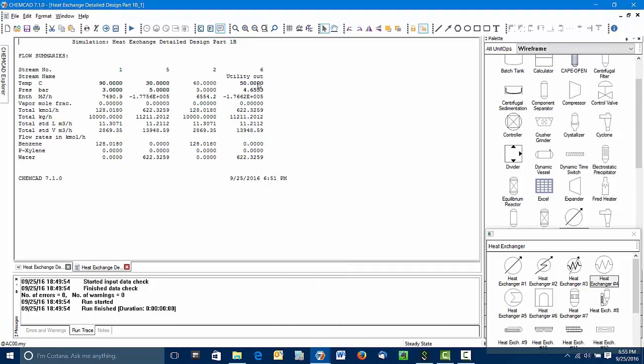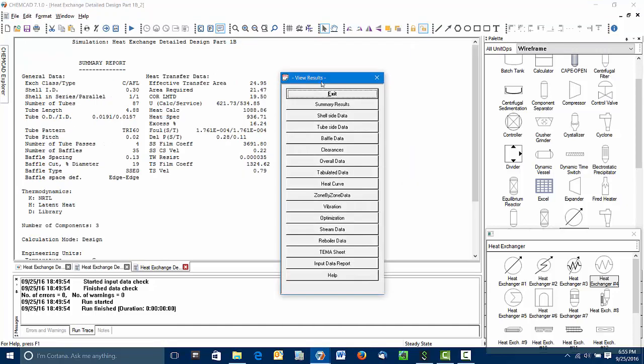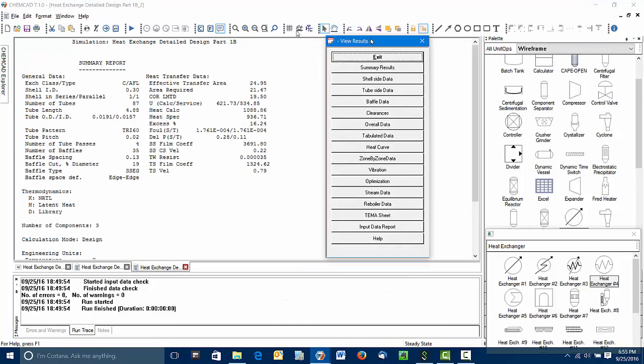I like to look at the summary results page where we get the heat transfer area. This is the heat exchange area as designed for the tube length, number of tubes, etc. The area required is what's needed to meet the design specification. So we've got a little bit of over design. So that's good.